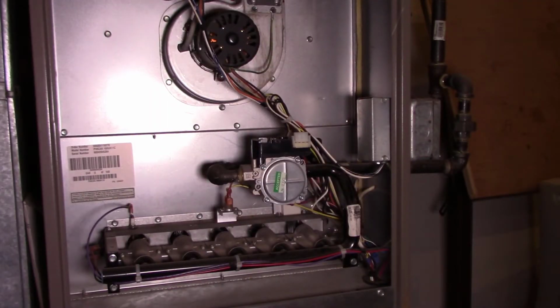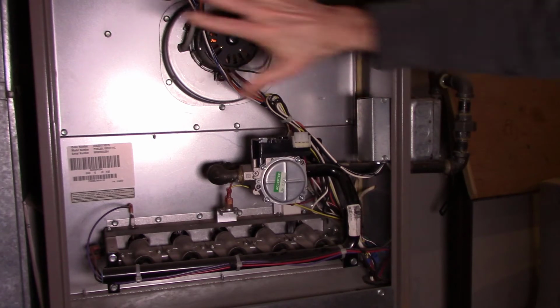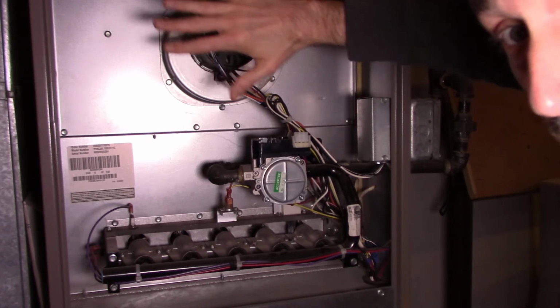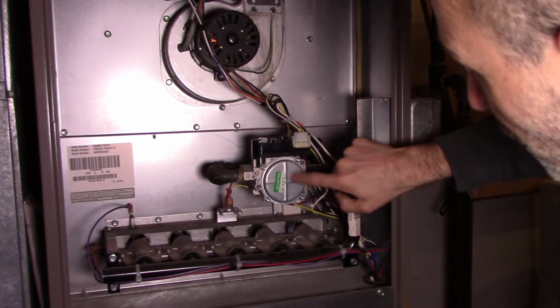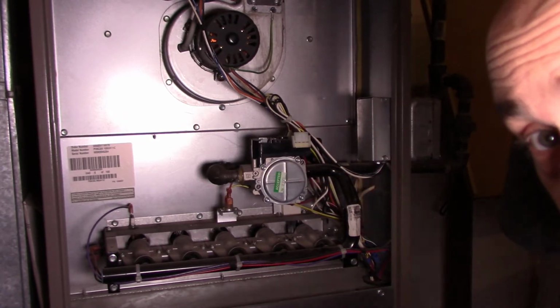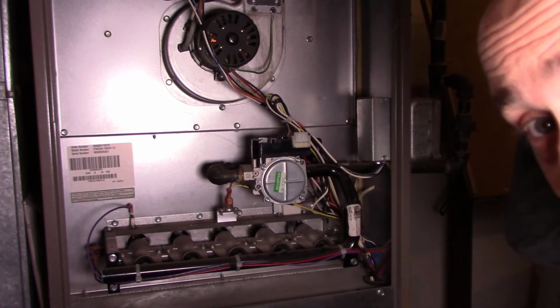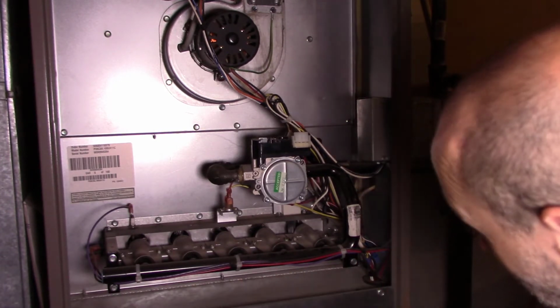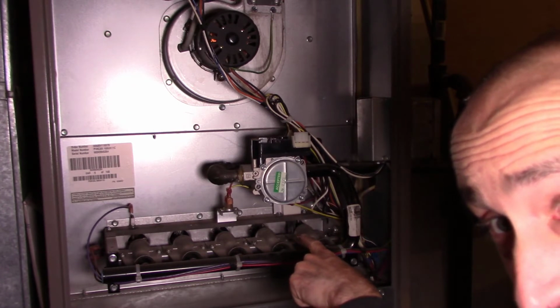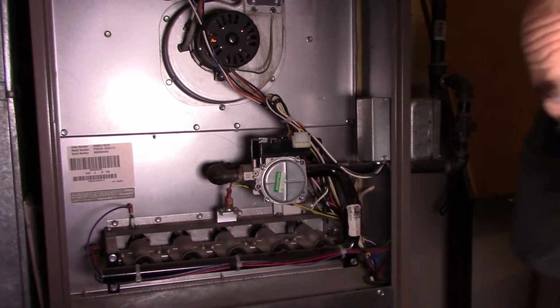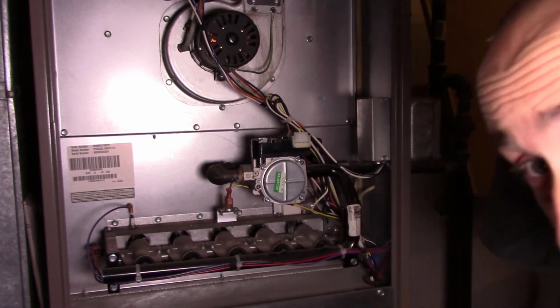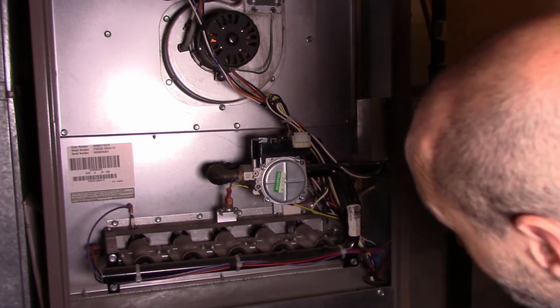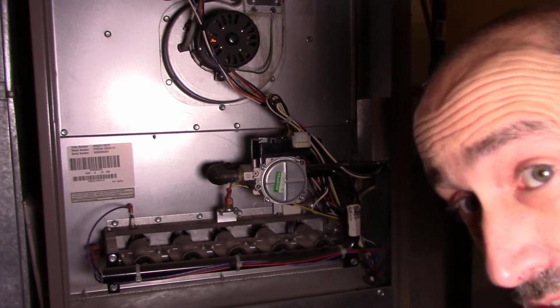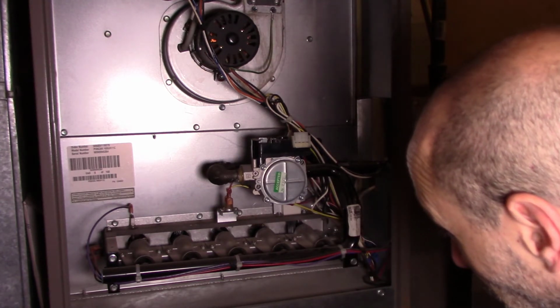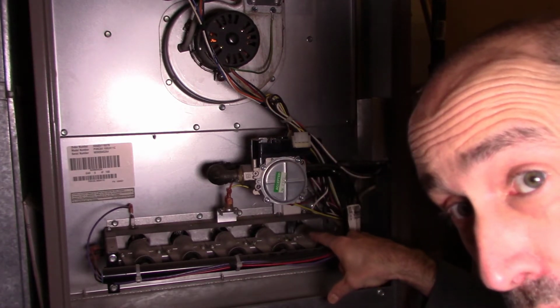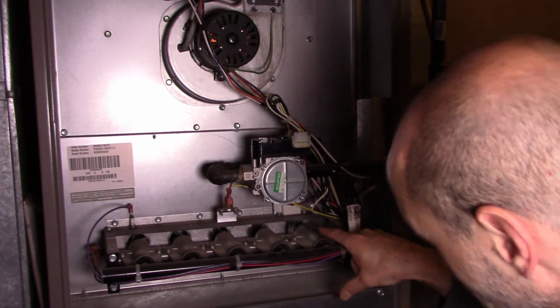Okay, so obviously the next thing that we need to address, now that we know our inducer motor and pressure switches are working, is the gas valve. Since you can't really see or hear gas, the next thing you want to do is look to see if that igniter either clicks or glows, depending on the type. You should start seeing that thing glow. If it doesn't glow or start clicking, then likely that part is broken, and that is a consumable part that typically needs to be replaced.